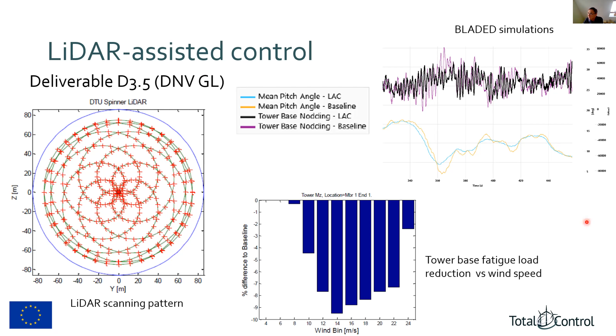Individual pitch control: the existing machine already has 1P individual pitch control using blade root sensors. The objective here is to look at adding 2P IPC, twice per revolution. This can reduce more loads. So rather than reducing just the low frequency nodding and yawing moments, you can also reduce the 3P nodding and yawing moments, which are much bigger fatigue drivers actually. So that can be quite useful for reducing loads.